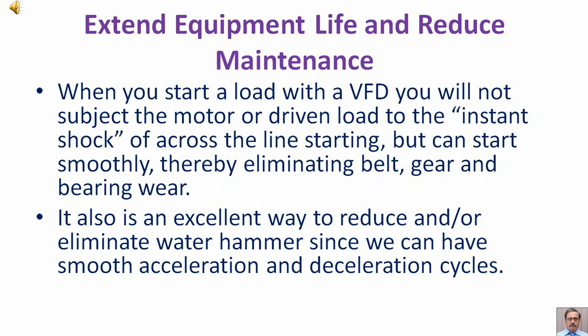When you start a load with a VFD, you will not subject the motor or driven load to the instant shock of across the line starting, but can start smoothly, thereby eliminating belt, gear, and bearing wear. It also is an excellent way to reduce and or eliminate water hammer since we can have smooth acceleration and deceleration cycles.